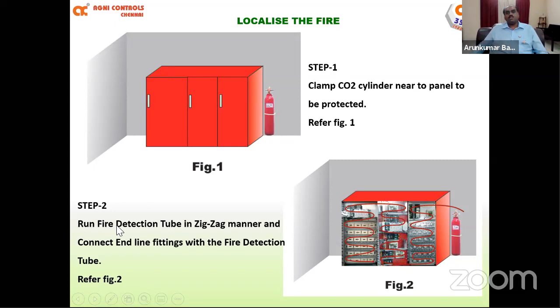The second step is to run the detection tube in a zigzag manner, or any manner available for the panel. In some areas we cannot use a zigzag manner, so we have to go only around the perimeter of the panel. We recommend zigzag because it increases sensitivity greatly—the system will respond to a very small fire or hotspot anywhere.